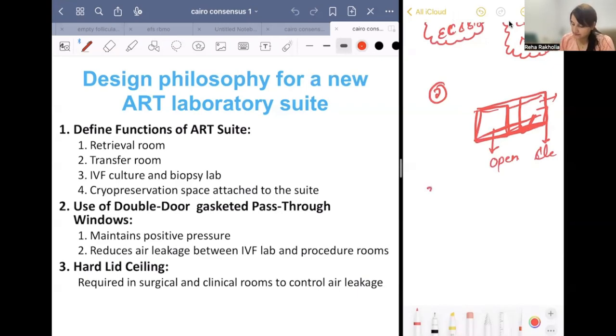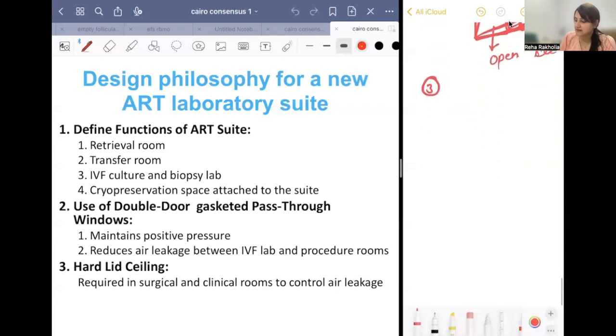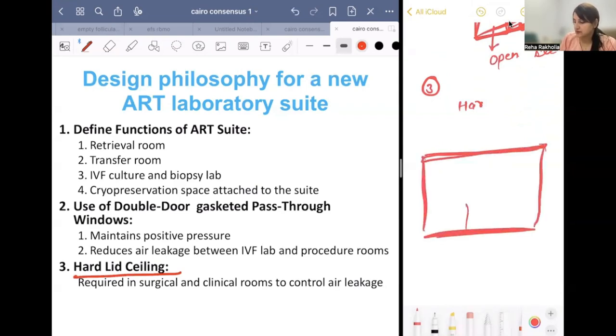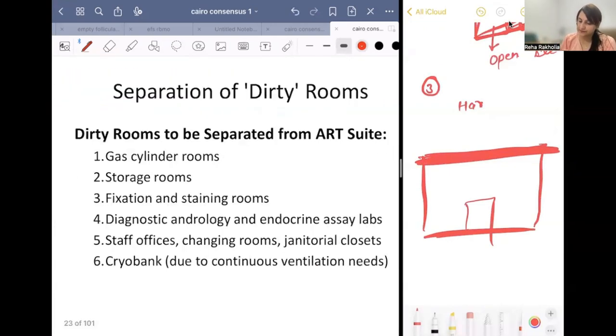Then third is hard lid ceiling. In surgical and clinical rooms, to control air leak, we need hard lid sealing of the ceiling - the opposite of the floor. This is the floor, this is the room, and this is the ceiling. The ceiling will be hard lid sealed so that there won't be any spaces for air to leak.